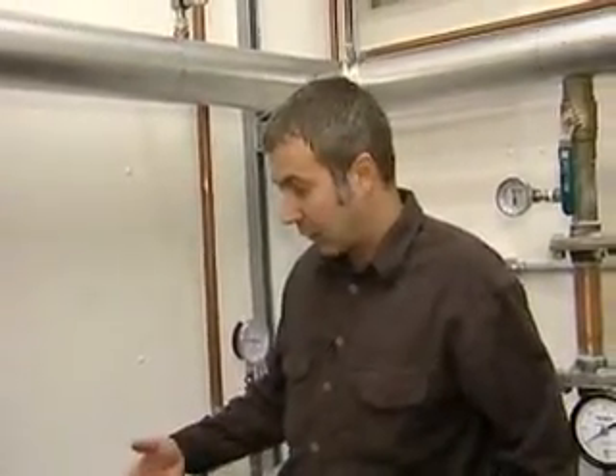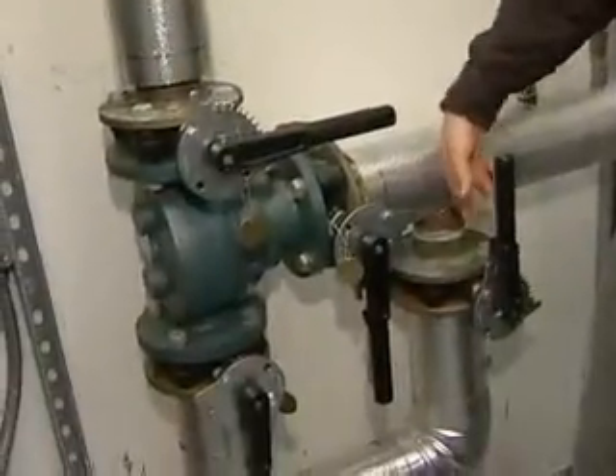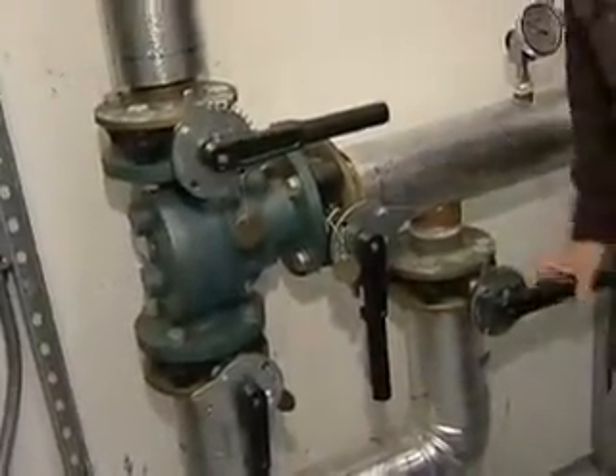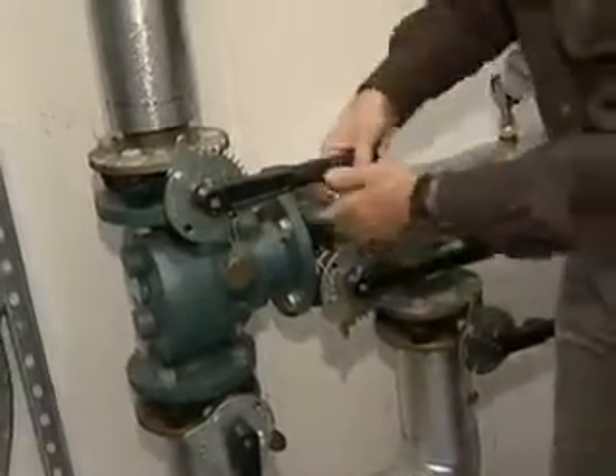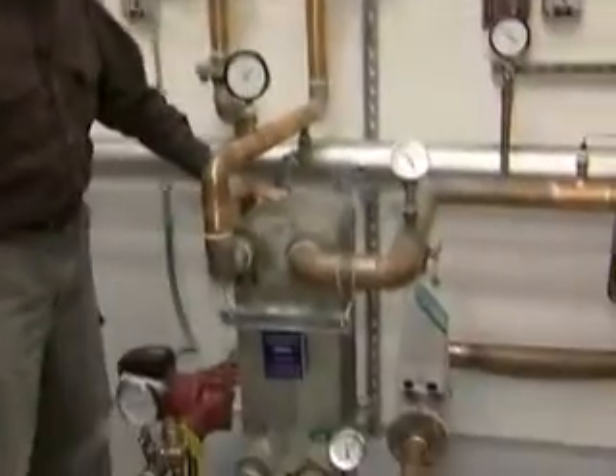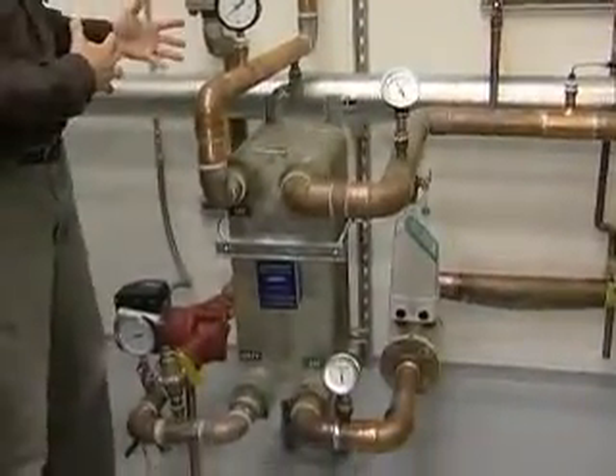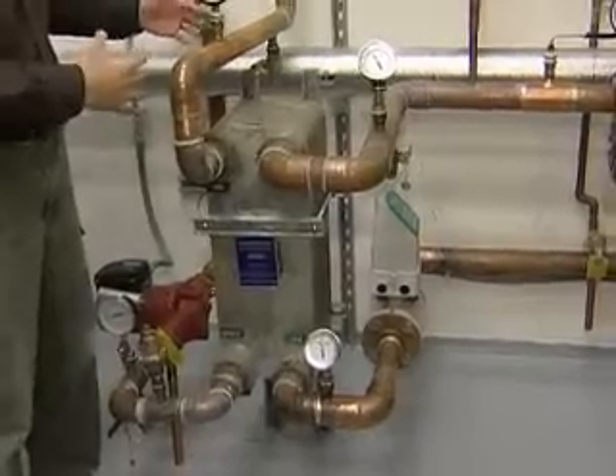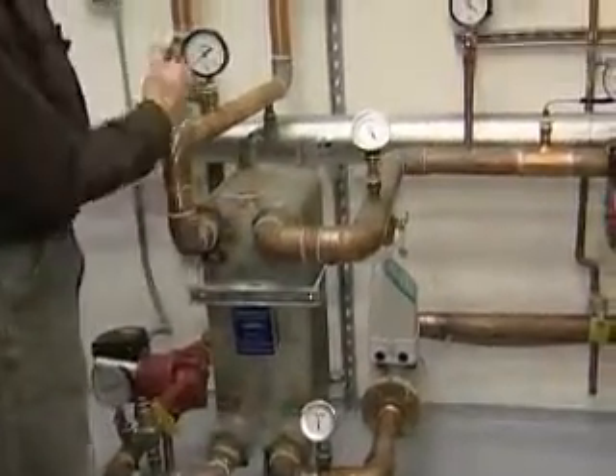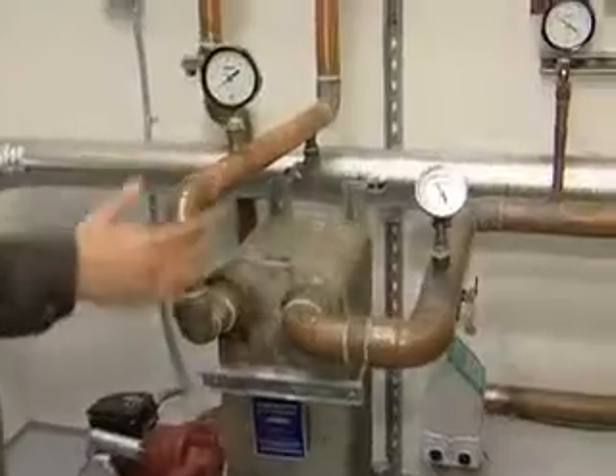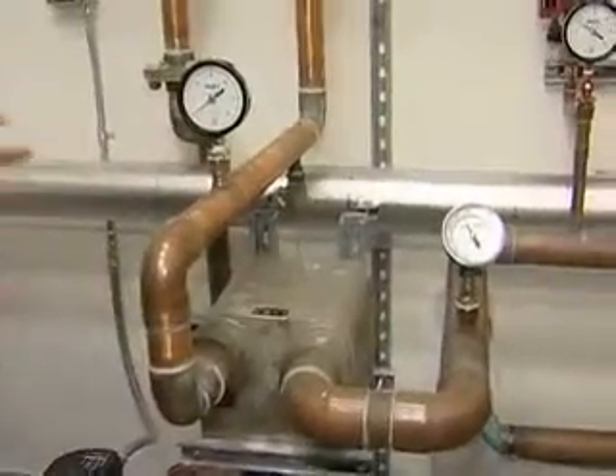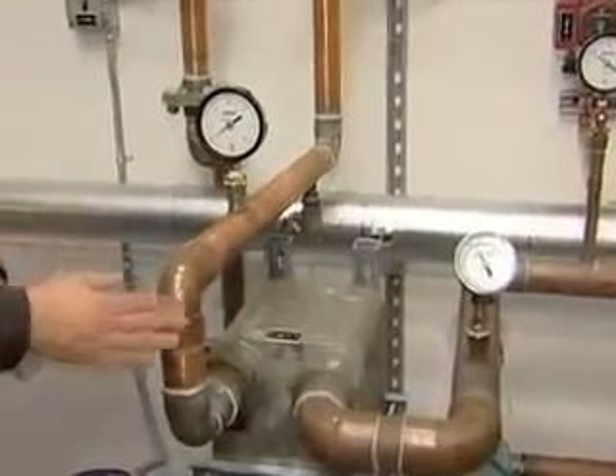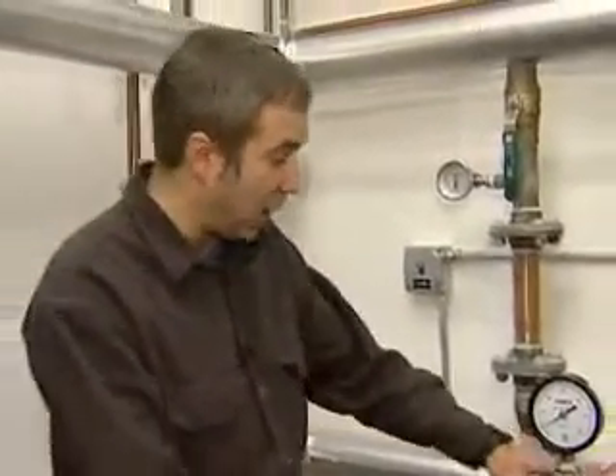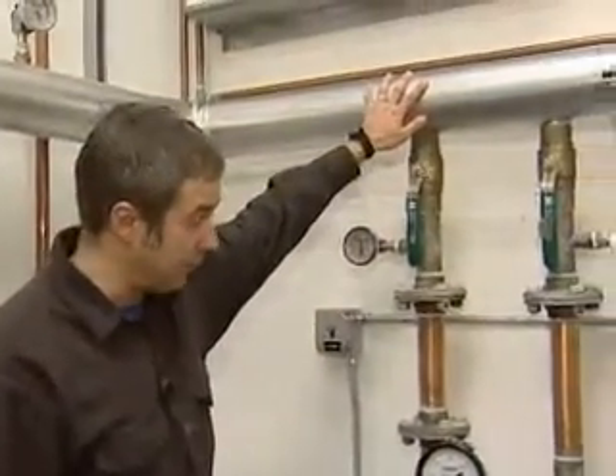And that allows you to keep the system online, and then this can be valved off, taken out, and repaired or replaced as required. So I'll return these valves to their normal position. Now the next part of the heat recovery system is a heat exchanger. This heat exchanger separates the coolant for the engine glycol cooling system from the piping that goes out of the building to the place where the heat is delivered to. So that way if we have a failure of the piping outside the building, we don't lose any of our engine coolant. So on the primary side, we're connected into the engine coolant.